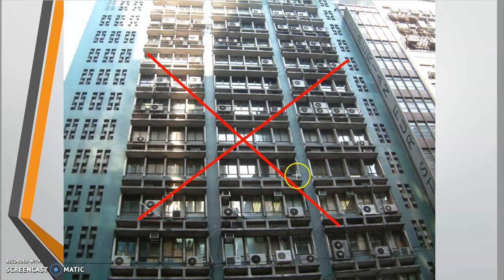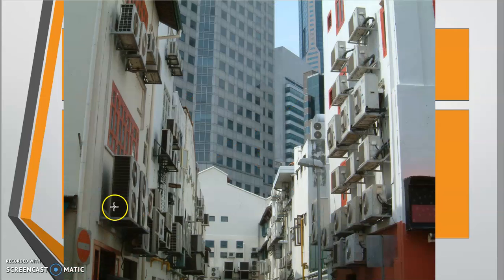If you are using a split unit system or vapor compression cycle unit, for example, we need a lot of outdoor units. So in appearance and aesthetic value, we don't want to see too many outdoor units on our building. As you can see, there are a lot of outdoor units visible outside of the building, compared to if you are using the VRV system. There is no outdoor unit we can see on the building, we just have to put it on the rooftop.